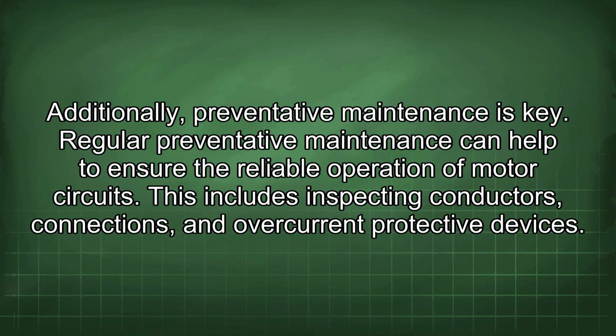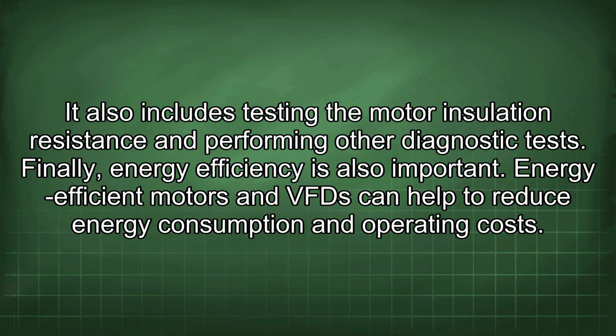Additionally, preventative maintenance is key. Regular preventative maintenance can help to ensure the reliable operation of motor circuits. This includes inspecting conductors, connections, and overcurrent protective devices. It also includes testing the motor insulation resistance and performing other diagnostic tests.